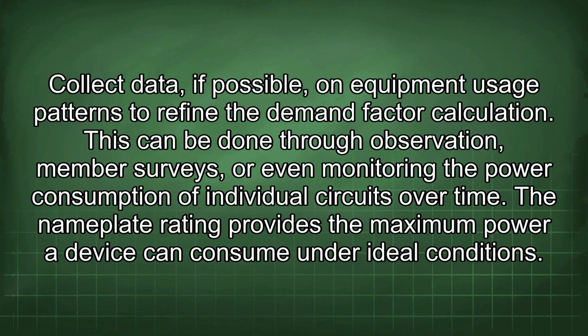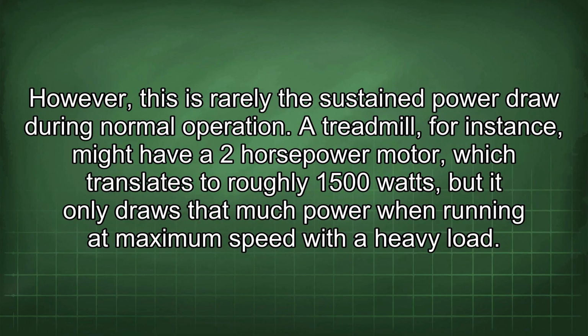The nameplate rating provides the maximum power a device can consume under ideal conditions. However, this is rarely the sustained power draw during normal operation. A treadmill, for instance, might have a 2-horsepower motor, which translates to roughly 1500 watts, but it only draws that much power when running at maximum speed with a heavy load.